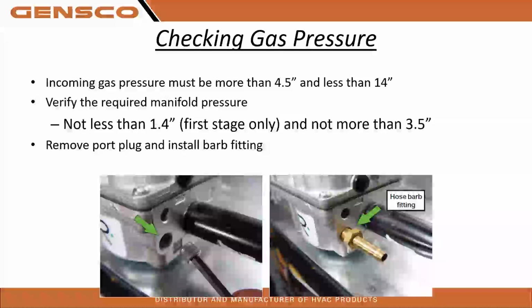Okay, verify the required manifold pressure. So not less than 1.4 for the first stage and not more than 3.5. Obviously, with mod furnaces, this can change a little bit. First stage on mod furnaces, I believe, is 0.7, for most models of that mod furnace. So it may change a little bit, but on a standard 2-stage gas valve, no less than 1.4, we've got to keep that burner face lit.